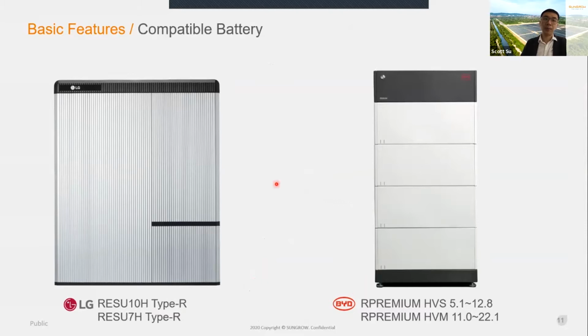Here are our compatible batteries. At the moment, we can be compatible with the LG 10 kilowatt hour high voltage batteries, but please pay attention. It's type R because LG has 2 types. One is type R, another one is type C. We can only be compatible with their type R. Type R means the communication method is RS485. Type C is CAN communication.